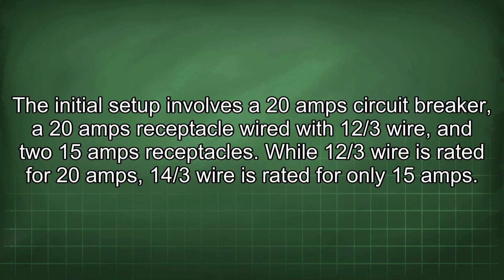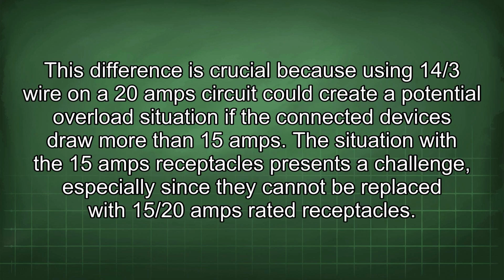The initial setup involves a 20 amp circuit breaker, a 20 amps receptacle wired with 12/3 wire, and two 15 amps receptacles. While 12/3 wire is rated for 20 amps, 14/3 wire is rated for only 15 amps. This difference is crucial because using 14/3 wire on a 20 amp circuit could create a potential overload situation if the connected devices draw more than 15 amps.